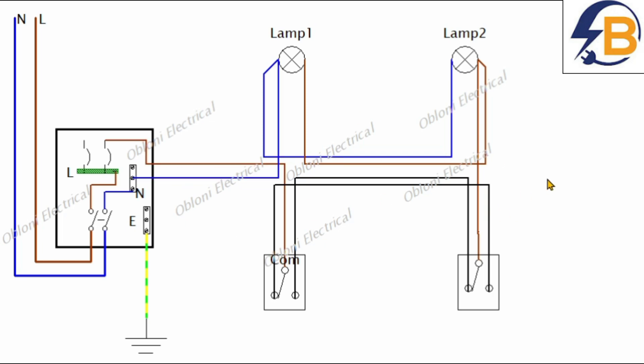Interpreting the wiring diagram is very simple because you can see everything. The two main wires from the electricity supply are live — connecting to the live input — and neutral — connecting to the neutral input. The neutral output connects to the neutral terminal bar and the live output connects to the live bar which connects to the breakers. This is simple to understand even for a beginner without much knowledge of electrical engineering. However, it is not usual to have a detailed wiring drawing for an electrical project; you normally find drawings as a plan or layout.